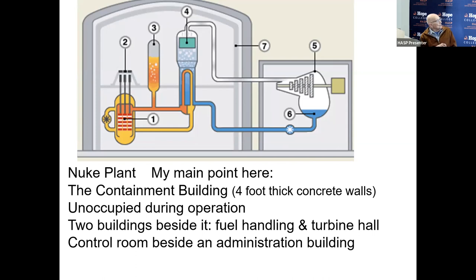Okay, one more time. The reactor sends super hot water to a steam generator, and it comes back cooler to become hot water again. It gives up its heat to some other water, and goes back to get heated again. And there's a big pump moving that water. There are the control rods in case there's a disaster, you shut it down. Now, these steam generators, they're not unlike the radiator in your car. You want thin-walled, skinny tubes and a lot of them. You want a lot of them with super hot water on the inside. You want them small, so you can have many to give off their heat to the other surrounding water. Huh, steam generators, small, thin-walled, they go bad from time to time.